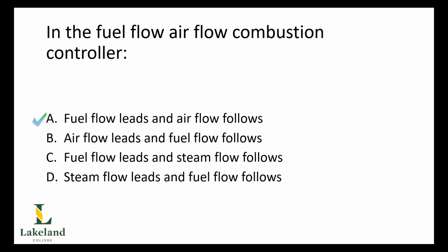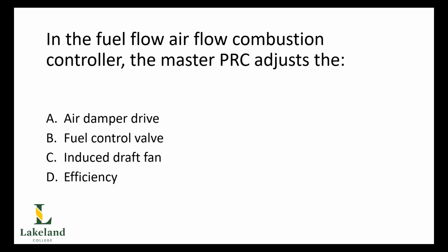And this is what we're describing regarding the control philosophy, in that the fuel required for the new firing rate will set the airflow, and then the airflow will adjust. I stress this again. It does not mean that the fuel adjusts first, then the air adjusts second. It doesn't mean that. It just means from a control perspective, not a physical one. That's really important to point out.